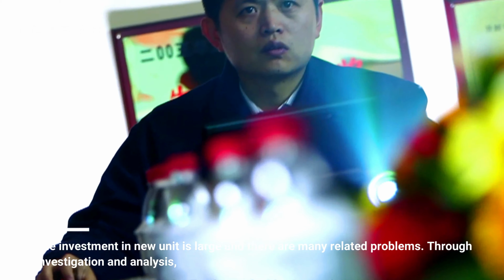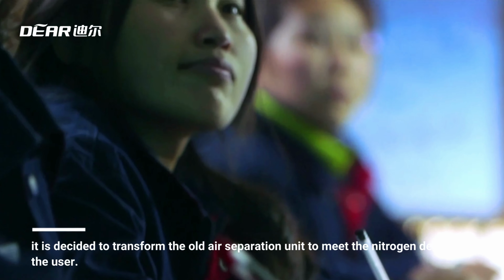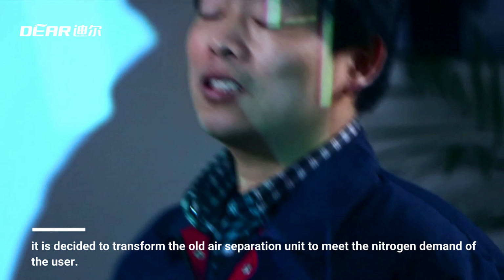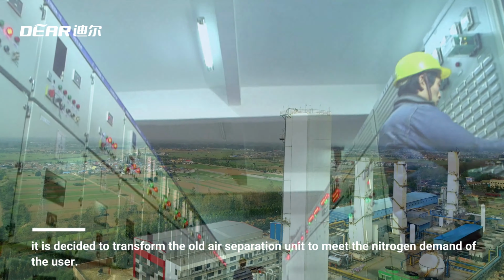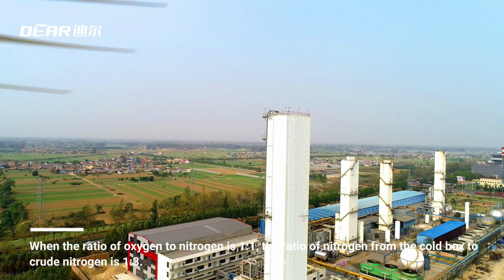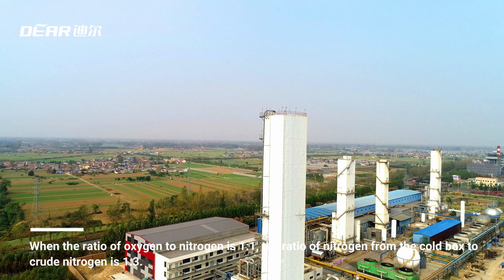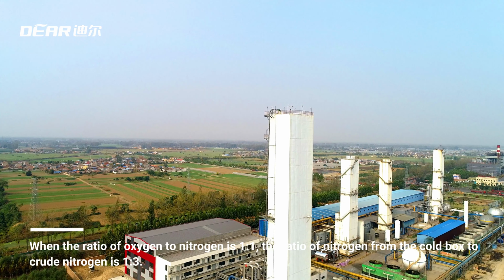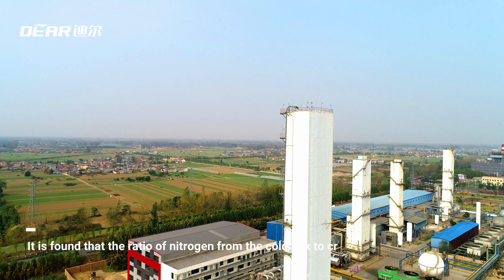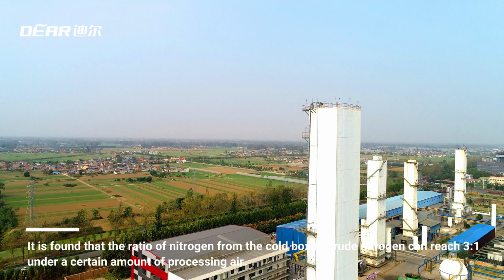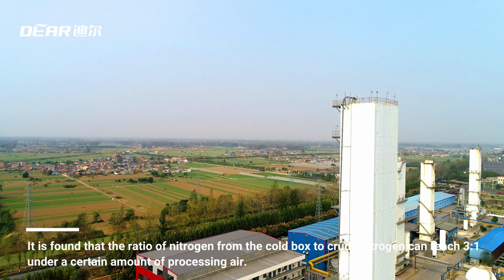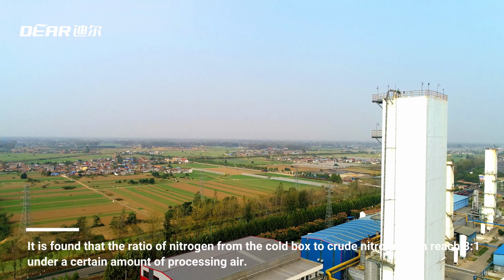Through investigation and analysis, it is decided to transform the old air separation unit to meet the nitrogen demand of the user. When the ratio of oxygen to nitrogen is 1-to-1, the ratio of nitrogen from the cold box to crude nitrogen is 1-to-3. It is found that the ratio of nitrogen from the cold box to crude nitrogen can reach 3-to-1 under a certain amount of processing air.